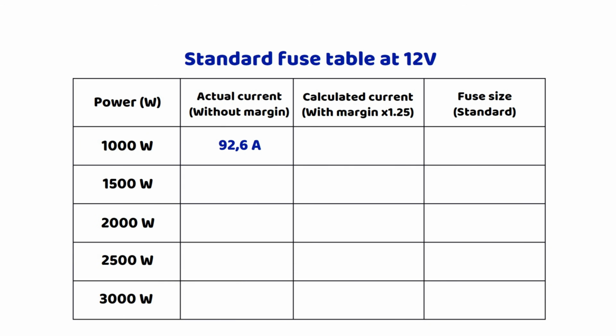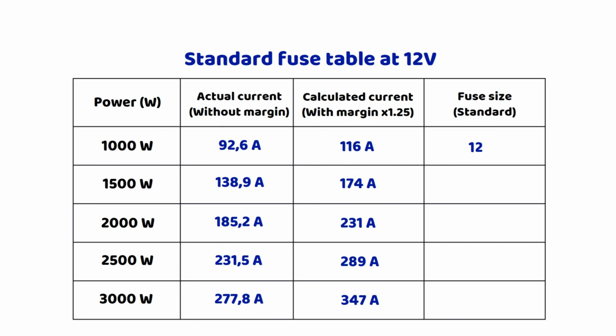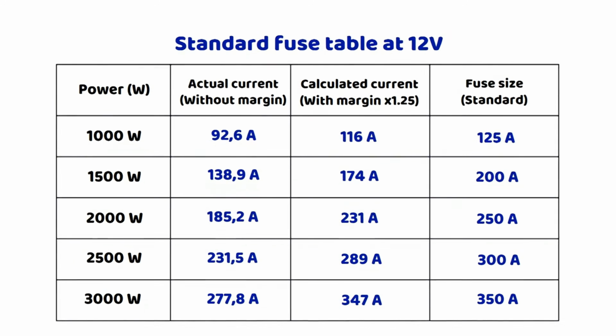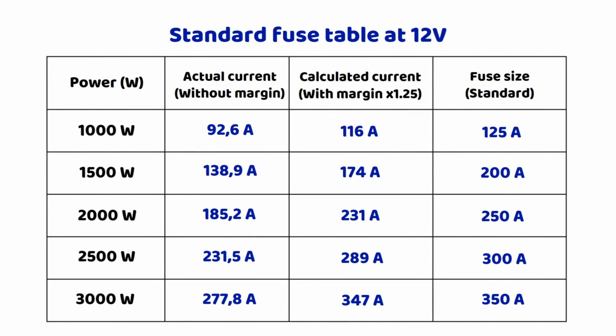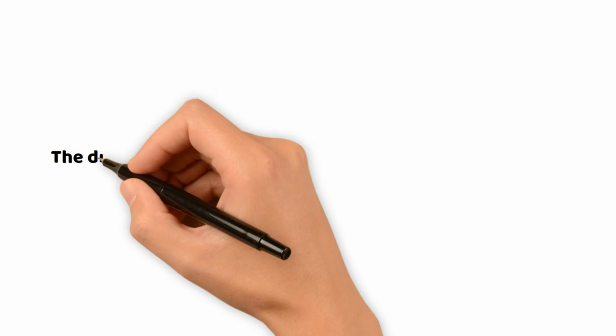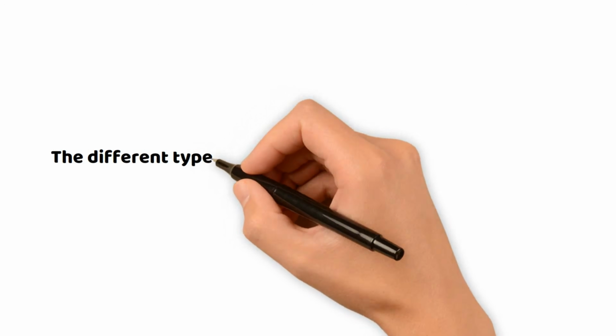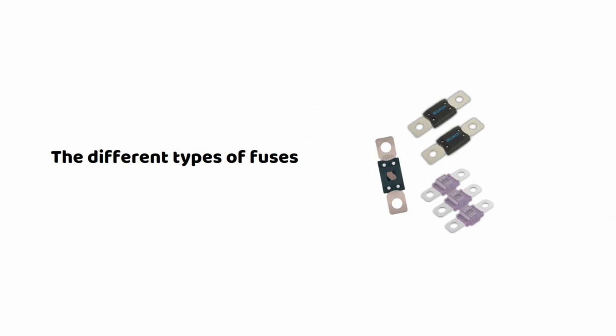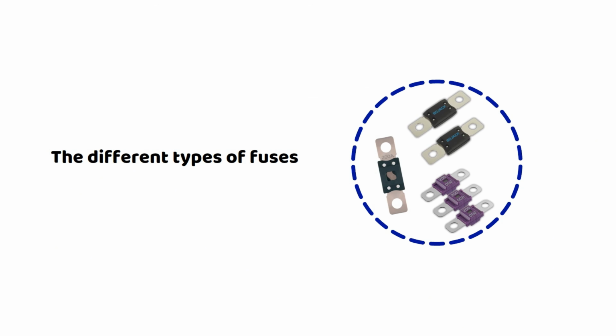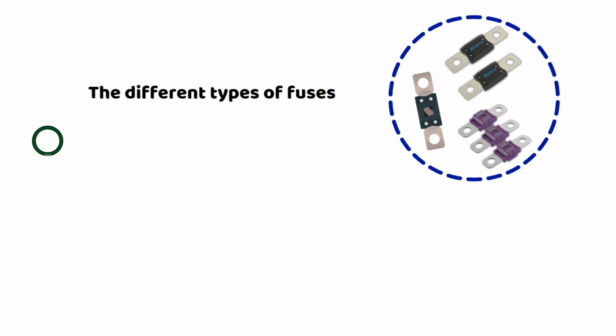To help you, here is a small summary table of the currents drawn from the battery, taking into account the 90% efficiency of an inverter and according to their rated power. There is also a second column with a 20% safety margin added, and finally the fuse rating in the nearest standard size. We can now talk about the different fuse technologies and other points to check besides its ampere rating. To secure your 12-volt or 24-volt installation, the choice of fuse type should not be made at random. Here are 3 essential technical criteria to check, as well as the types of fuses suitable for your circuit.